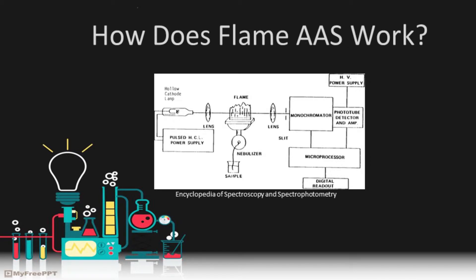A diagram of a typical flame AAS is shown here. The sample is fed through a tube into a nebulizer, which converts the solution to a mist before passing the atoms through the flame. The high-energy flame atomizes the sample and converts the mist to a gaseous state. At the same time, a hollow cathode lamp containing your analyte of interest creates an optical path through the flame, and attenuation of the light can be detected as the atomized iron absorbs light of a specific wavelength. This difference is detected using a photo tube detector after passing through a monochromator to separate the iron's optical path from unwanted background radiation. The most commonly used photo tube detector is a photomultiplier, which converts incoming photons into electrical signals, and these signals are converted into a digital readout.